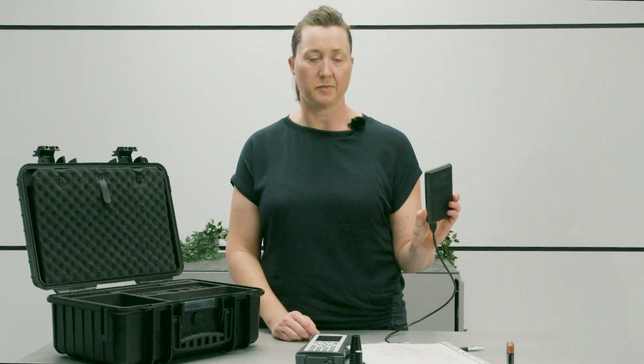I have also prepared 4 rechargeable batteries and the rechargeable battery pack. The device is suitable for operations at ambient temperatures of 0 to plus 40 degrees Celsius. Keep the measuring station free of ferromagnetic materials, for example tools, that may influence the measurement.